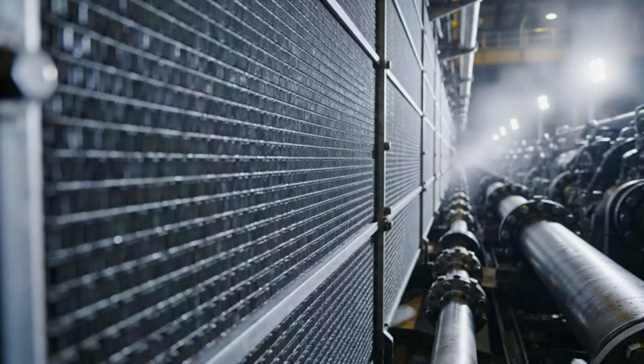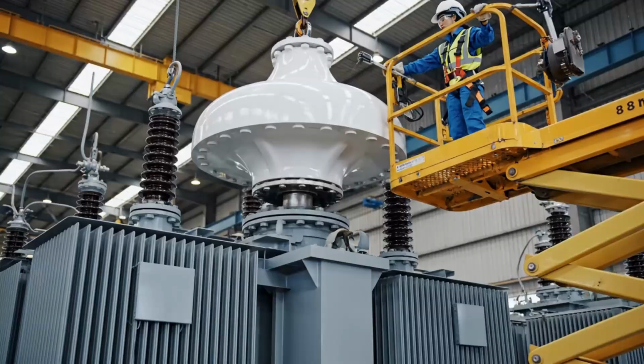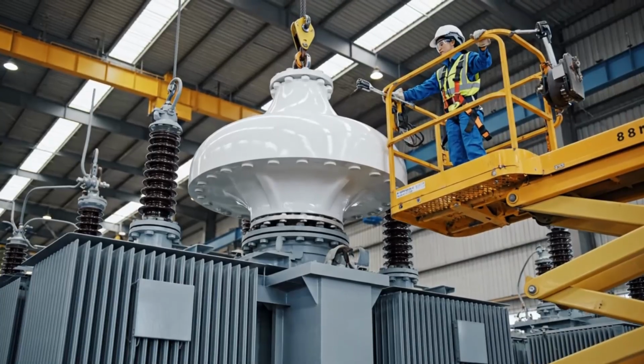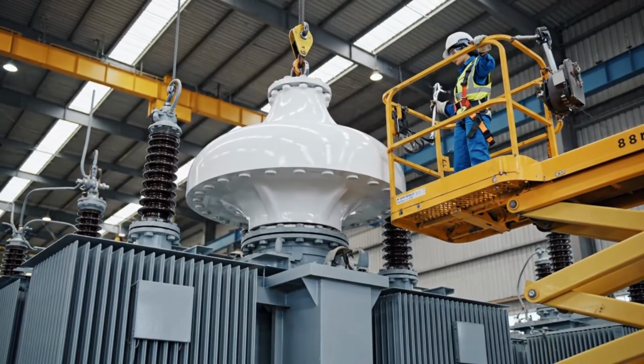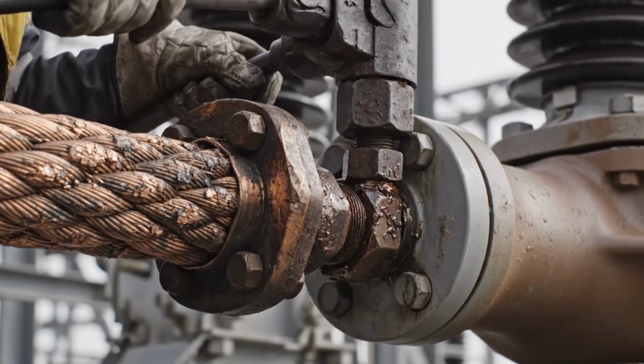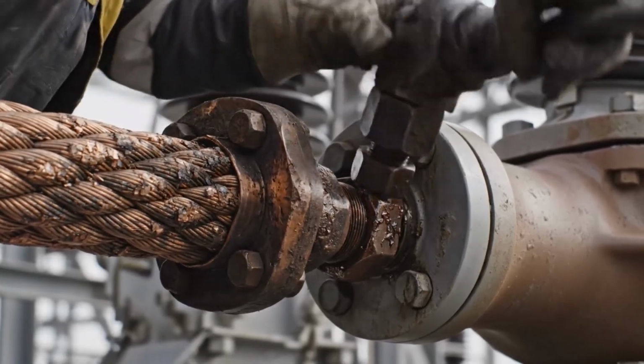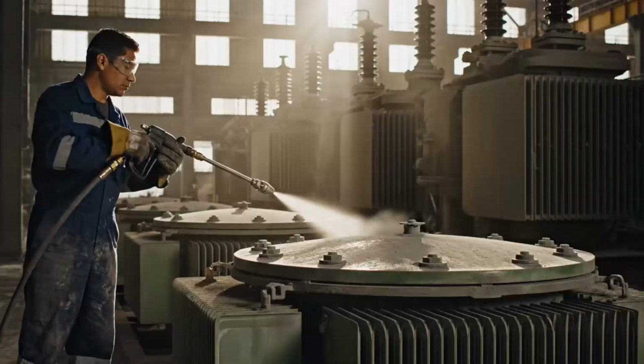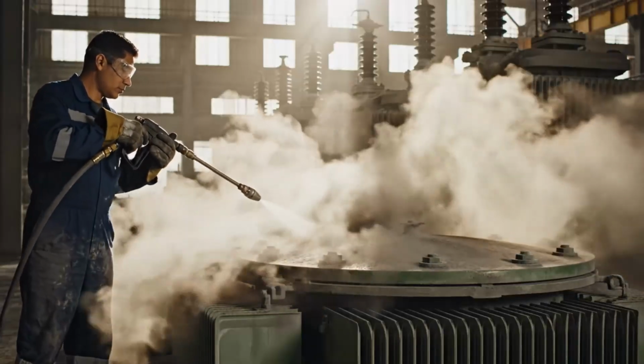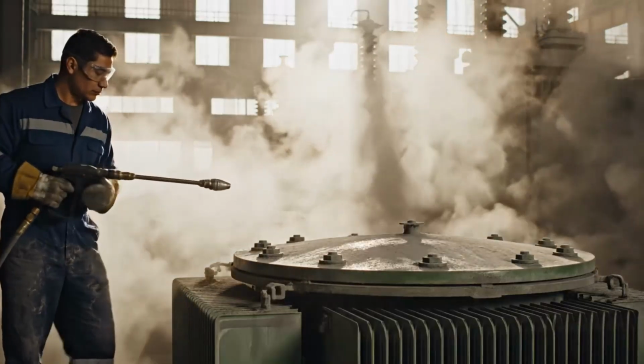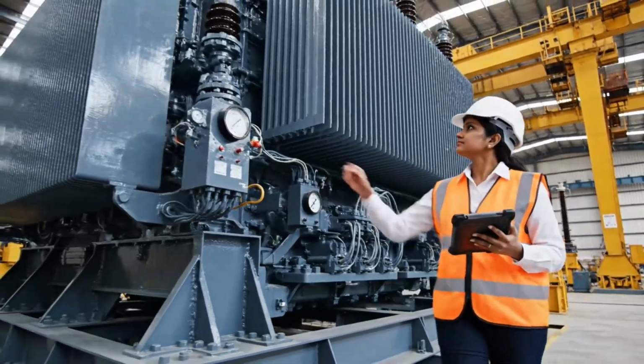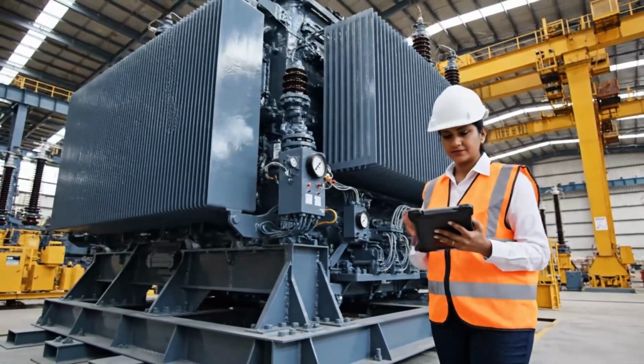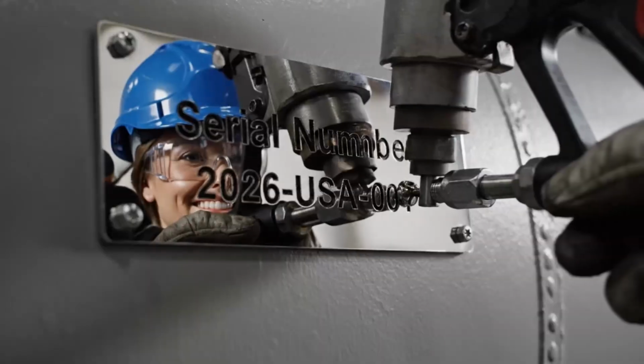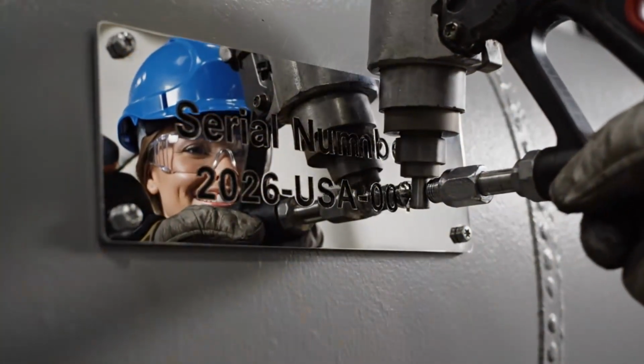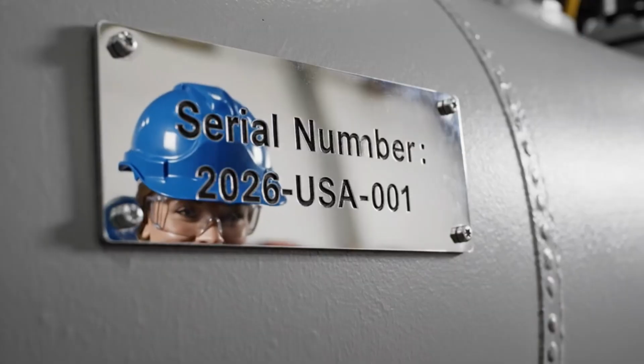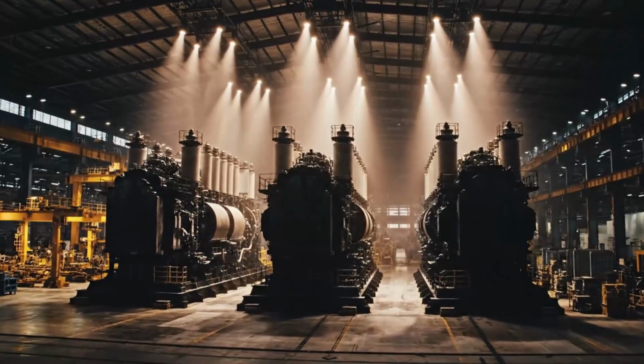While the internal components are being dried, another part of the factory is building what can only be described as a steel fortress. The tank of a high-power transformer is not just a box. It is a reinforced pressure vessel designed to hold tons of oil and survive 50 years of brutal weather. Huge plates of carbon steel are welded by robotic arms that ensure not a single microfissure exists. Every weld is checked with ultrasonic sensors and fluorescent dyes. After welding, the tank is grit blasted and coated with an electrostatic epoxy paint that makes it immune to corrosion, whether it's headed for the salt air of the coast or the freezing humidity of the north.